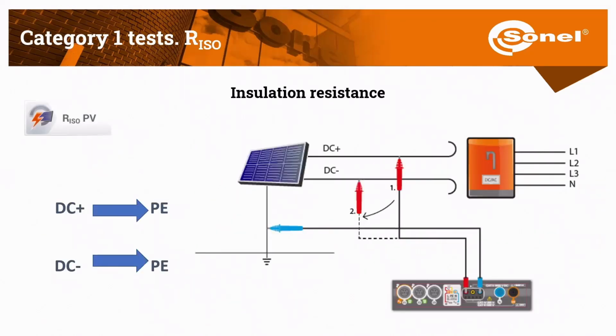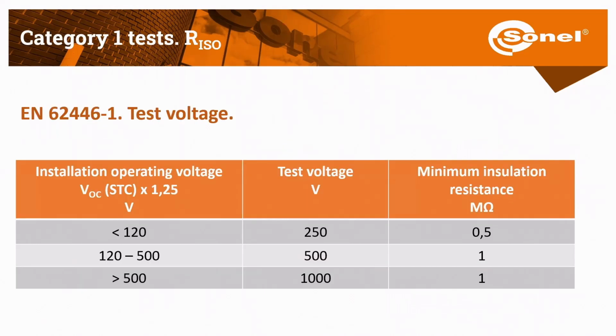Insulation resistance of the DC side, where you are checking first of all the plus of the DC, and the second is the minus of the DC side of the installation. And the test voltage, installation operating voltage, and it describes what should be the test voltage on the measured installation, and what is the minimum resistance requirement so that we can say the installation complies and is okay.